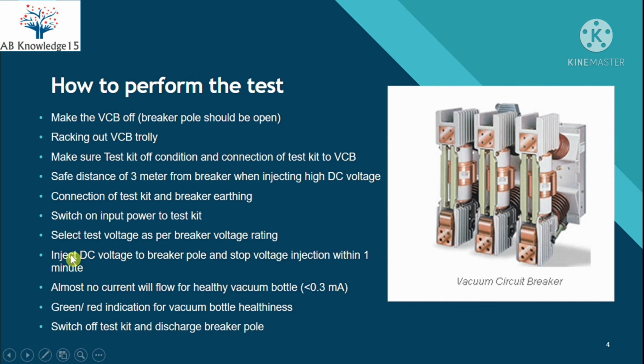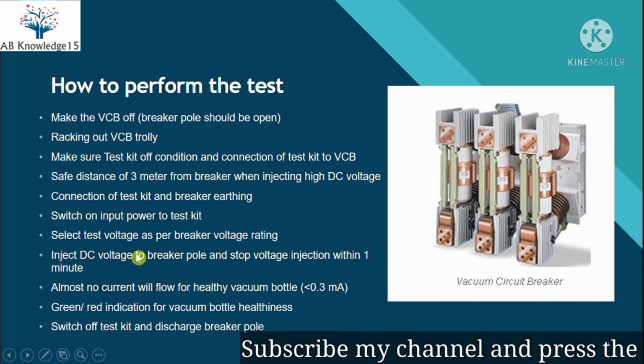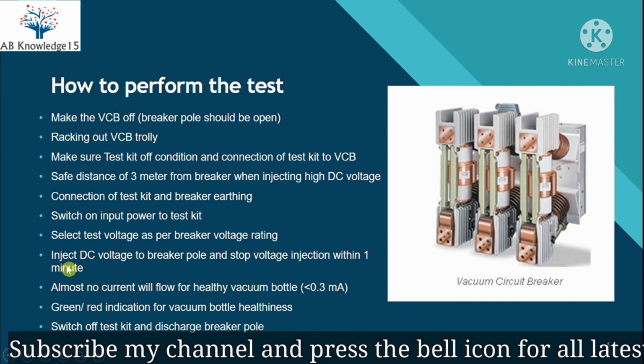Now inject the DC voltage to the breaker pole and stop the voltage injection within 1 minute. Here you will inject the high DC voltage to the breaker pole. The voltage injection should be stopped within 1 minute because this is high DC voltage, and if it is continued after 1 minute, then you will face other problems. So it is advisable to carry out this test within 1 minute.